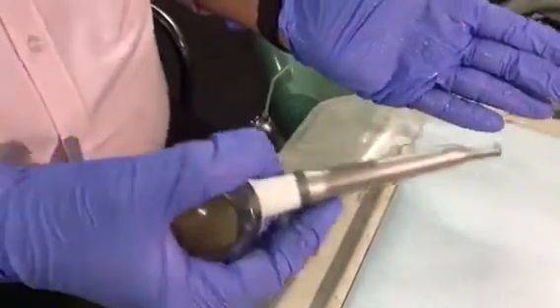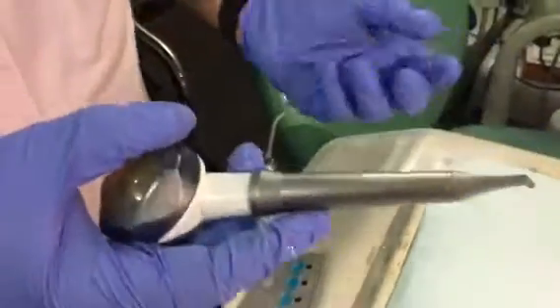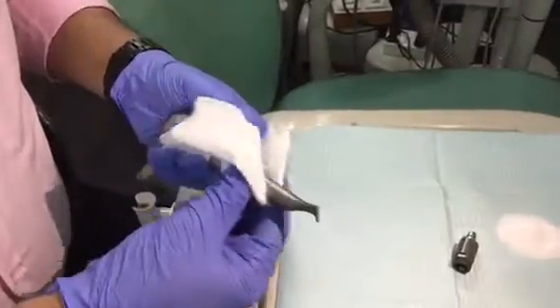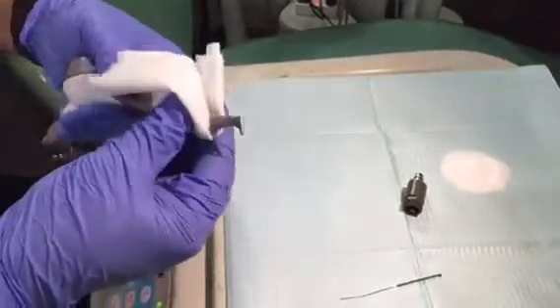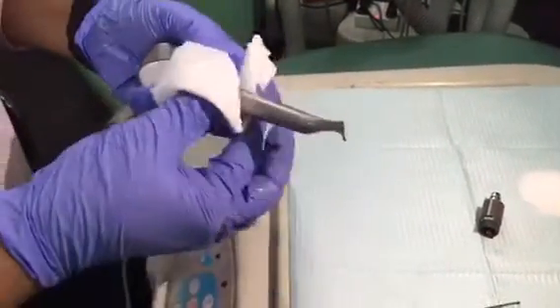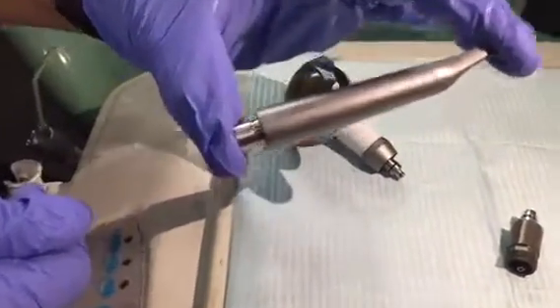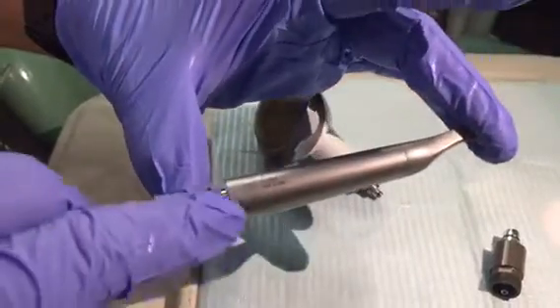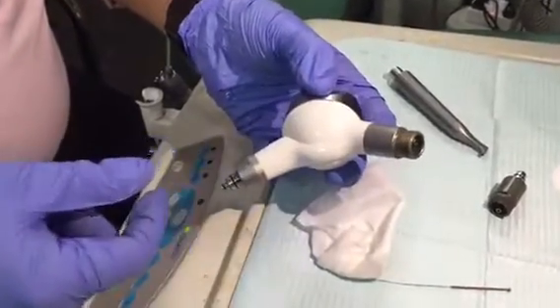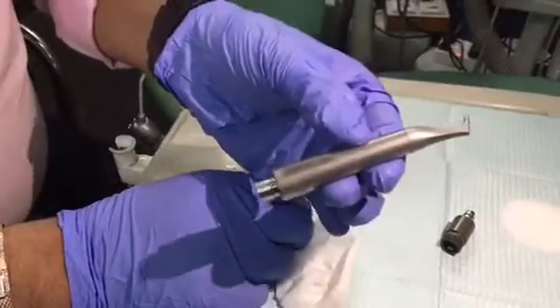If you want to double-check, you can attach the head of the handpiece and then check — water should come out from here as well. This shows that neither the handpiece nor the head is blocked. To maintain the head, always wipe it clean with an alcohol swab or a wet wipe. This handpiece head is autoclavable, so you can put it in an autoclavable pouch and place it inside the autoclave. Never put the body in an autoclave — it has plastic components that might melt. Only the head is autoclavable.